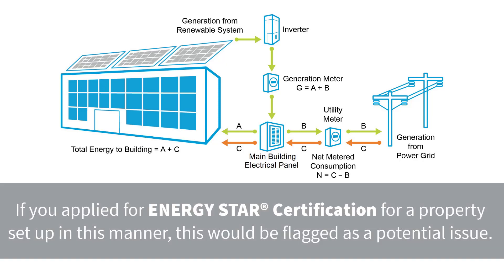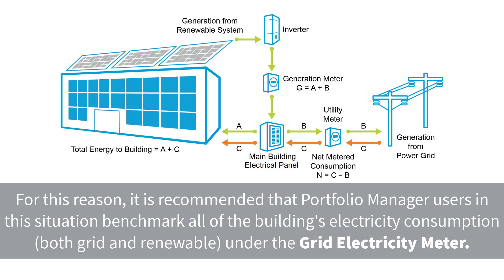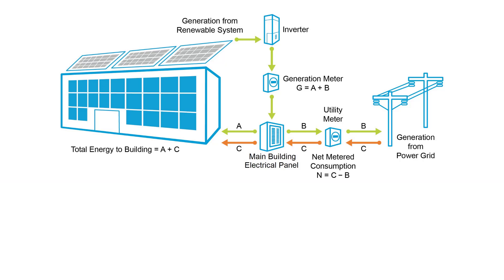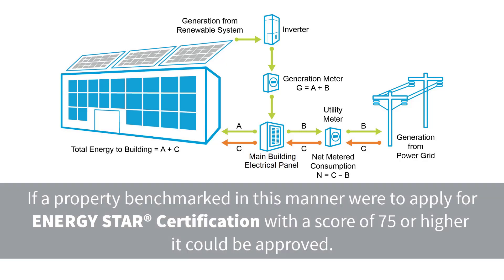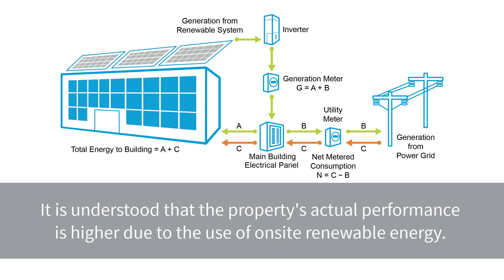If you applied for Energy Star certification for a property set up in this manner, this would be flagged as a potential issue. For this reason, it is recommended that Portfolio Manager users in this situation benchmark all of the building's electricity consumption, both grid and renewable, under the grid electricity meter. This is a conservative approach, as it keeps the property from receiving the credit associated with on-site renewable electricity as compared to grid electricity. But if a property benchmarked in this manner were to apply for Energy Star certification with a score of 75 or higher, it could be approved, since it is understood that the property's actual performance is higher due to the use of on-site renewable energy.